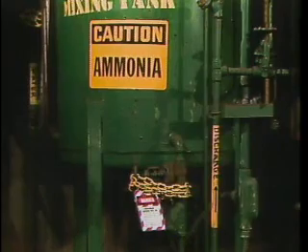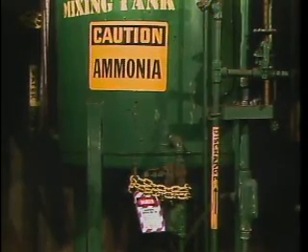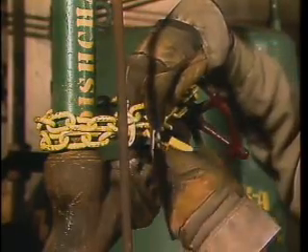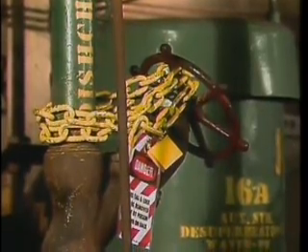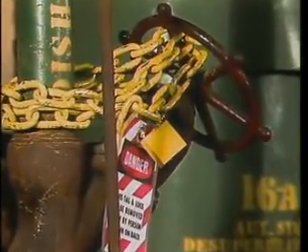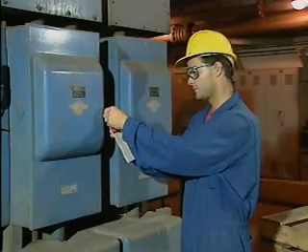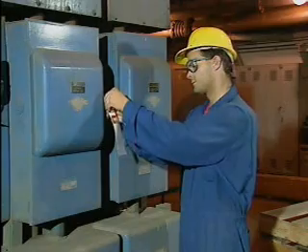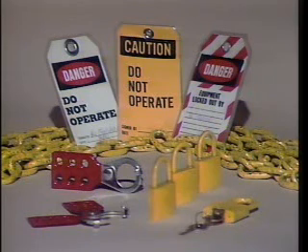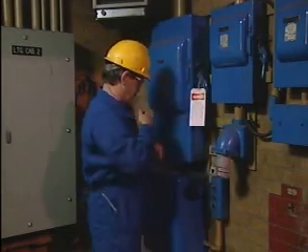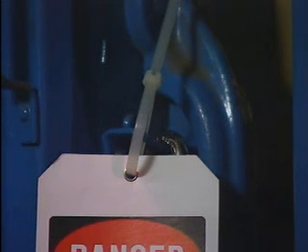In addition, they must be capable of withstanding the environment they're used in. When locks are used, they must be substantial. That is, they must be strong enough so that they can't be opened without the key unless excessive force or unusual procedures are used. When tags are used, they should warn against hazardous conditions that can occur if the equipment is improperly re-energized. Tags must carry standard warning labels such as "Do not operate," "Do not close," or "Do not energize." Tags must be attached to the equipment with non-reusable self-locking devices that are capable of withstanding a force of 50 pounds.